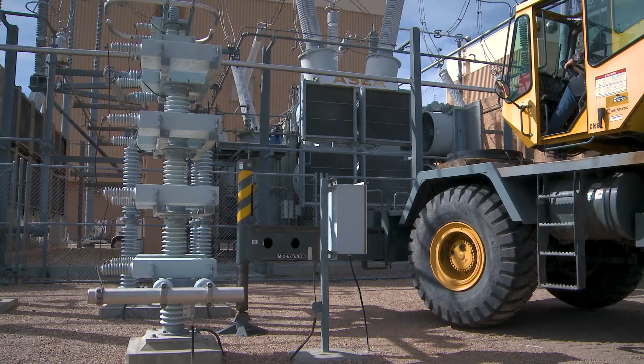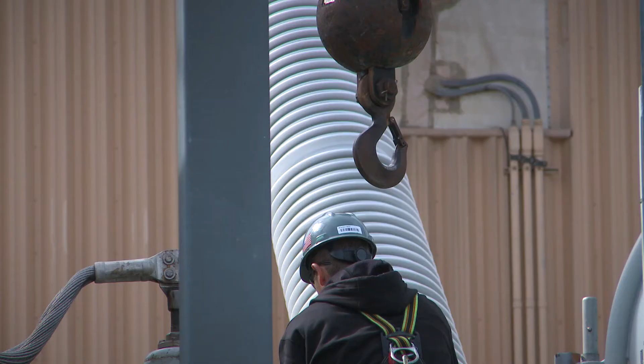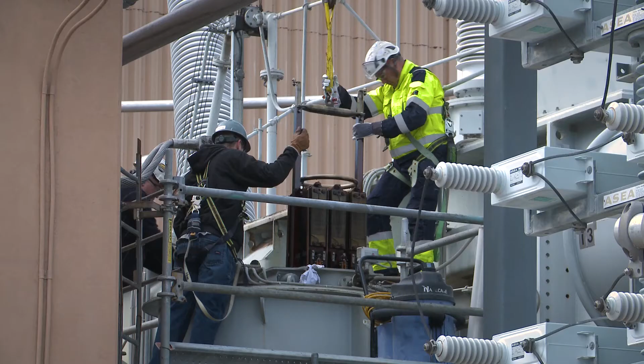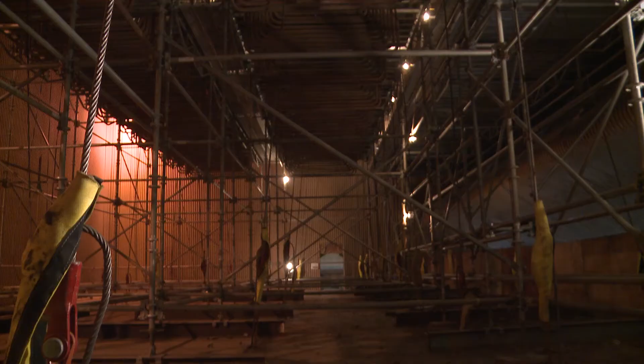Major work also occurred in the switchyards of both the generating station and at the Adelanto terminal on the California end of IPP's DC transmission line. A switchyard circuit breaker replacement project continued, and a 9-day bipole outage during the spring maintenance period allowed installation of a new transformer at the Adelanto substation, replacing a transformer that failed. IPP has also ordered spare transformers for the DC substations to guard against any future failures.